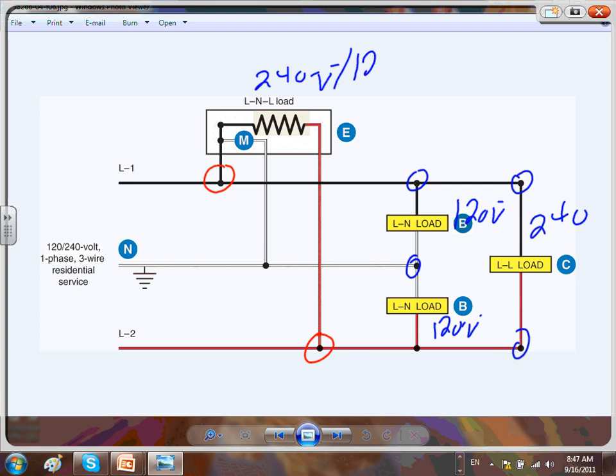This makes it a 240/120 volt system — typical of dryers. The motor runs at 120 and the heating element burns at 240. Dryers work by creating heat and rotating the drum. The rotation comes from a motor and the heat from a heating element. That's why you send three conductors to the dryer: two hots and a neutral.